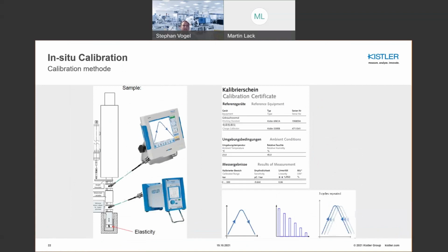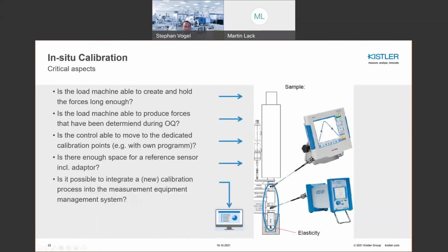When calibrating, you have to see that there are different possibilities to do so. Typically, when you create your own process, you describe the calibration process you are using, the measurement points you're using, and you define what has to be calibrated, on which load points, for example, and so on.